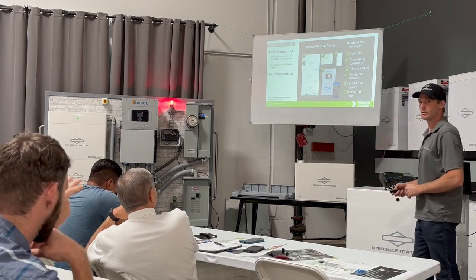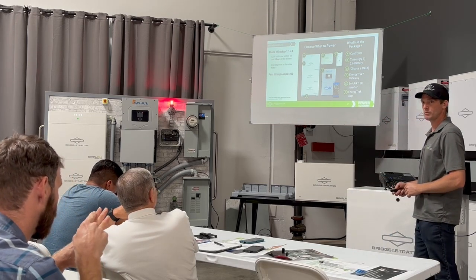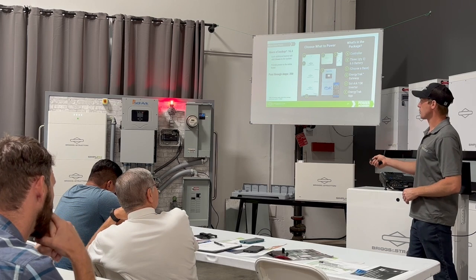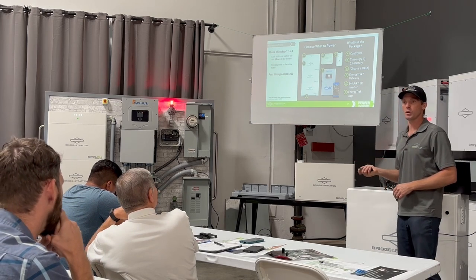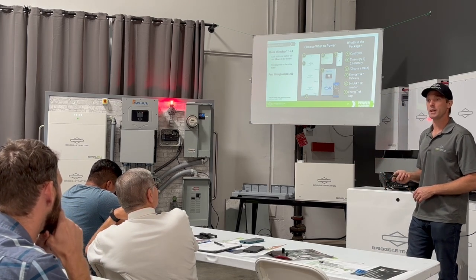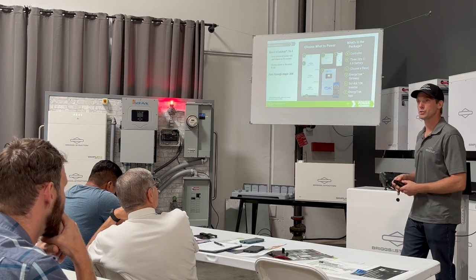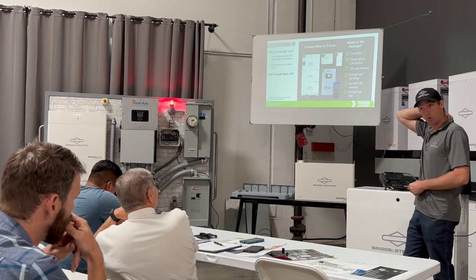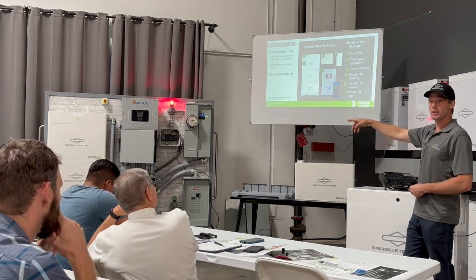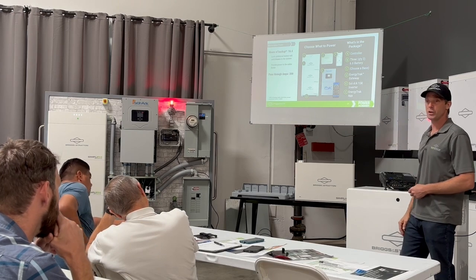It can't handle all 3 of those backup methods at the same time. The only time the generator port on the Sol-Ark is going to work is if the utility port doesn't have any power on it. So as soon as there's 240 volts of power on the grid port, the relay for the gen port is blocked.